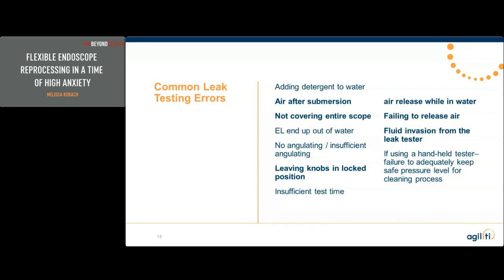I have seen a number of people release the air while still in the water, which can lead to fluid invasion in a scope that does not have a hole in it. There are little O-rings in the connector from the leak tester that hooks onto the venting port. While these may get worn over time, they may still be good and leak free. But once you release that and that pressure moves away, it can pull water right into your electronics area.